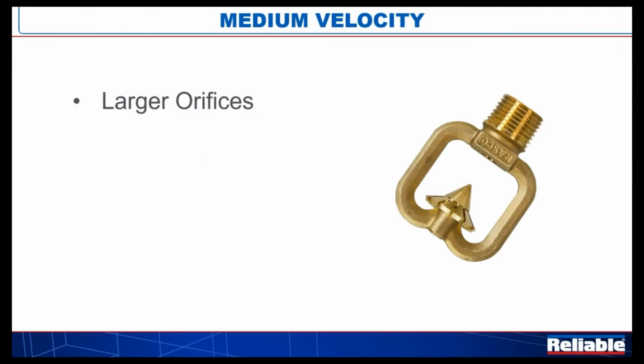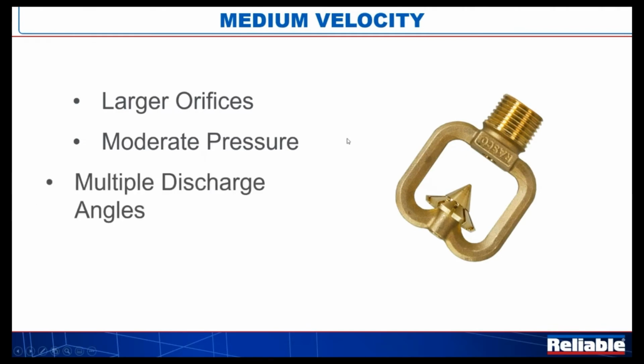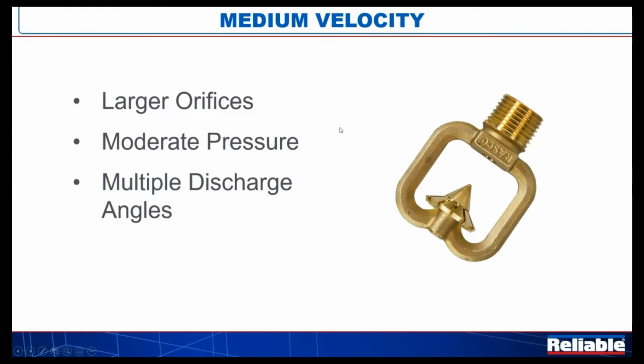We open the orifice size a little bit. Moderate pressures, these are going to be in, let's call it the 20, 25, 30 to 60 range-ish. If you want to try to at least apply a number, think in terms of that. Again, multiple discharge angles. That discharge angle is typically driven by the splitter cone and that deflector. And we'll see in a little bit.